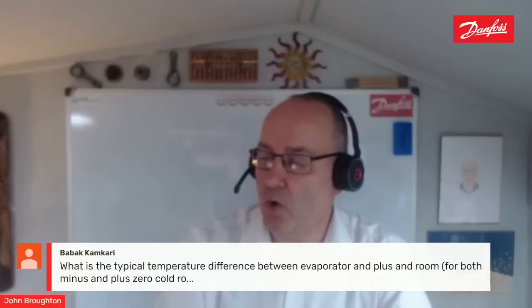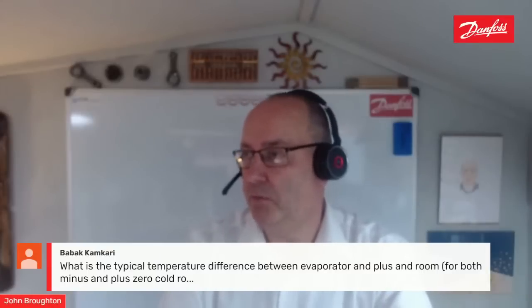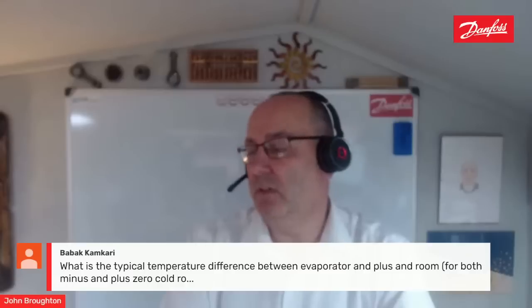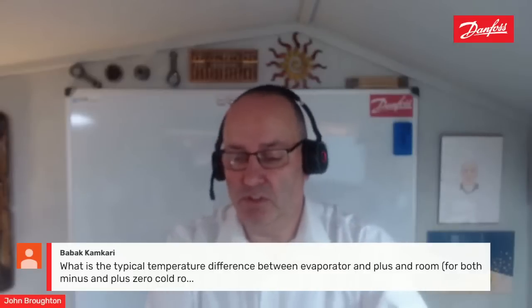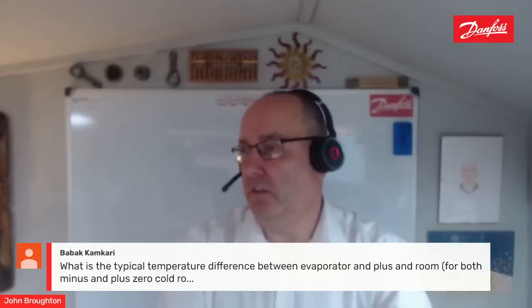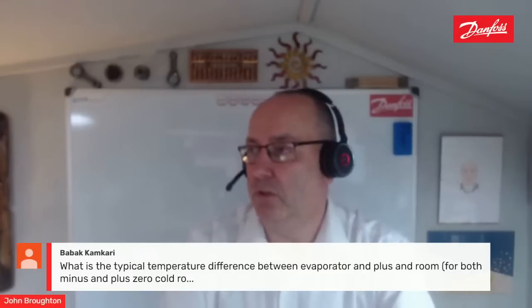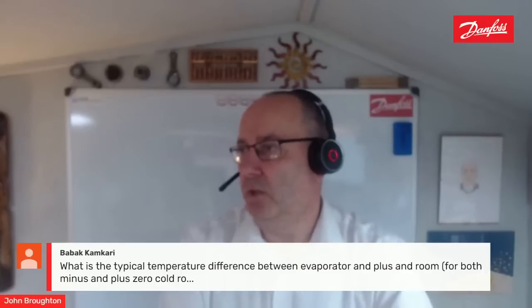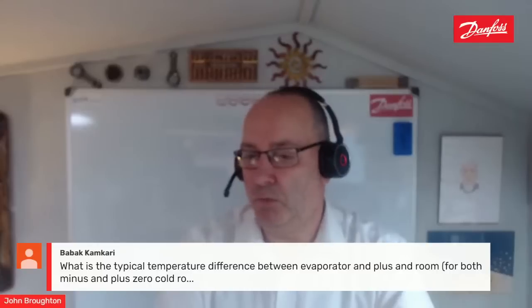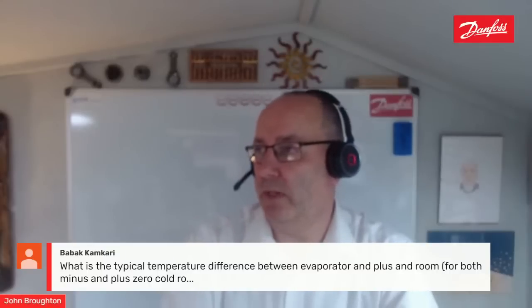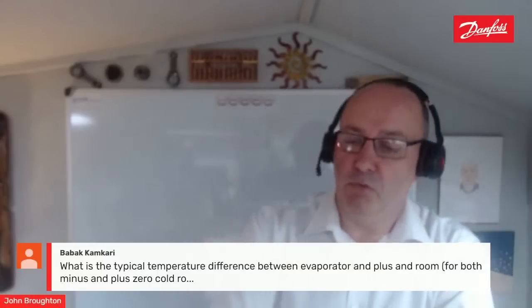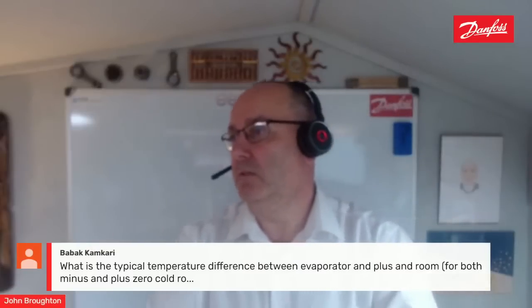If you have a very low humidity, then you lose weight from the product because you're pulling moisture out of it, which for your customer is not good, because generally he sells fruit, vegetables, all those commodities by weight. So you don't want to pull moisture out of the product and reduce its weight. Also, if you remove moisture out of the product, then you will reduce the quality of that product. So I hope that answered that question, Babaka. Just give us a thumbs up if it did.